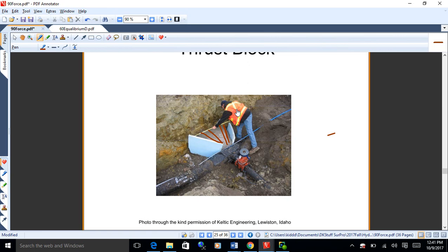You know, this isn't like plumbing in your house. These are 8-inch ductile iron lines. They're heavy as can be. So you don't like flanging. You probably use them on valves and stuff, but there's an intermediate option called a mechanical joint. It has like a sliding collar and then a compressible gasket that you bolt up to a flange type connection. And you can add things to that.